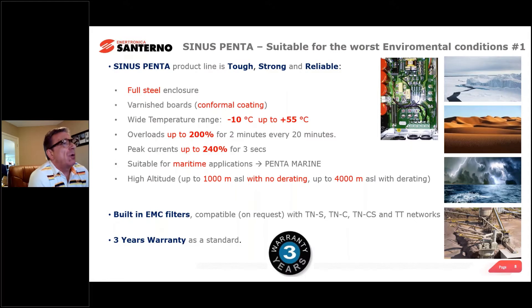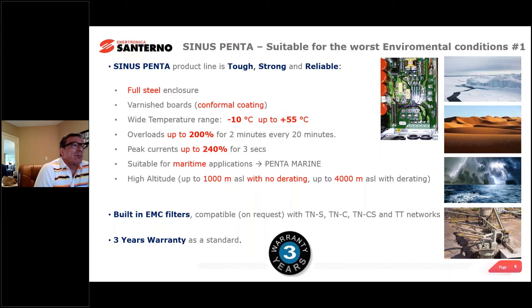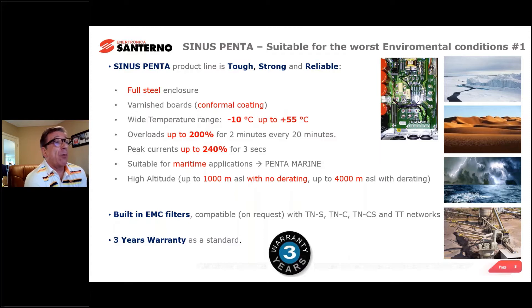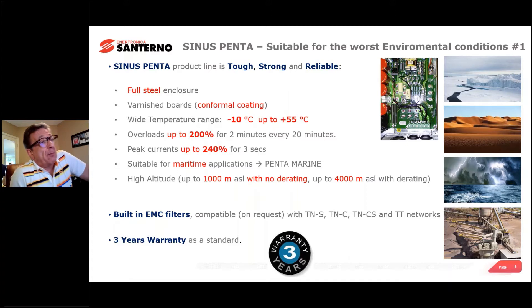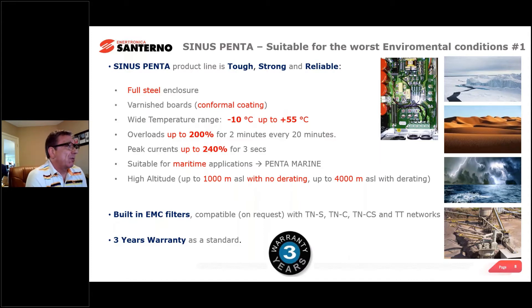When looking at products for industrial or oil patch use, the Santerno VFD comes in a full metal enclosure — no plastic box. The boards are varnished or conformal coated, meaning a type of polymer or varnish applied to the power electronics. In a noxious environment like a wastewater treatment plant with caustic in the air, this prevents copper from corroding. It has a very wide operating temperature — minus 10 to plus 55°C without extra heating or cooling. I've used this product in Northern Alberta packaged with heaters down to minus 45°C.